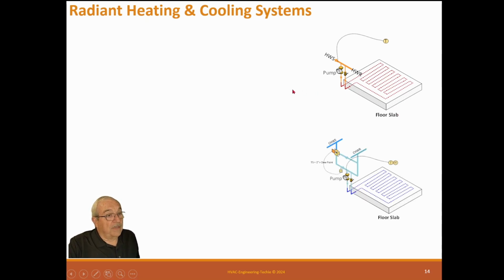That's why it's called radiant heating into the space. And we also have now something called radiant cooling, which does the same thing, and the only difference is the cooling water cannot be below dew point, or else it condenses water in the slab. So other than that, it's the same thing. It cools down at night, and in the daytime it absorbs. Instead of the radiation going off of it, the radiation is going into it. Very comfortable, it works very well.